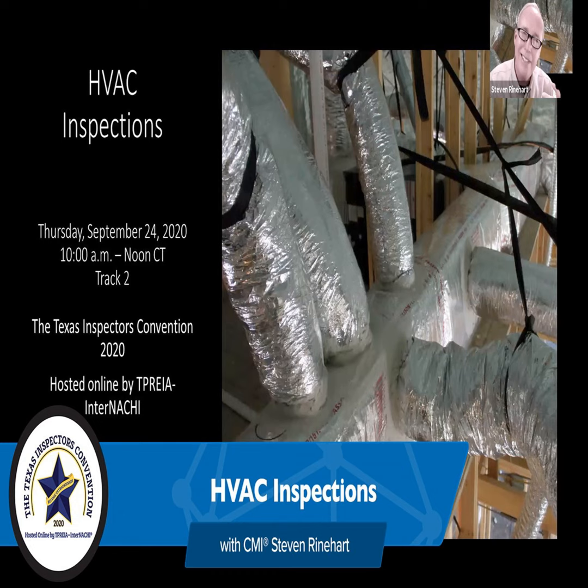Requirements for gas heating also: combustion air, dilution air, shut-off valves. We talked about access to shut-off valves. Unlike a stove where it might be behind there, not easy to get to, I should be able to slide it out and get to it. I should not have to move anything in the mechanical closet to get to the shut-off valve. It's usually on the side, easy to get to. Do I test them? Not unless I really suspect something, any more than I would test the shutoff under a bath lavatory. Some guys check every shutoff. I don't unless I really suspect something is wrong.